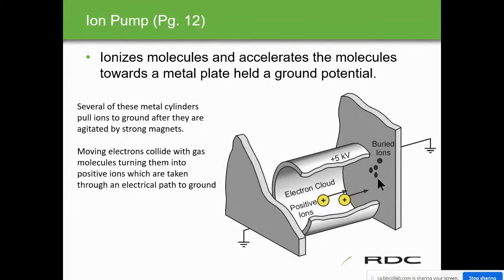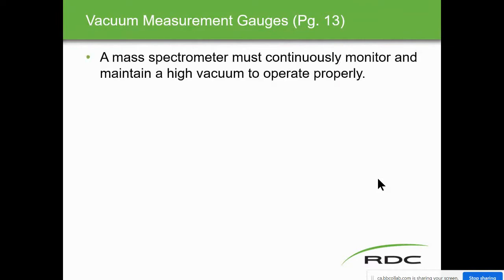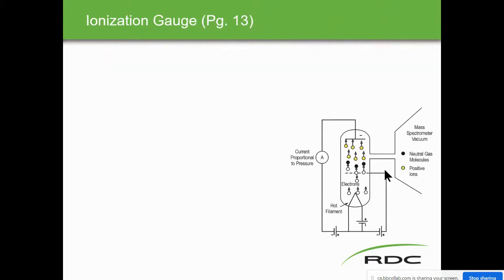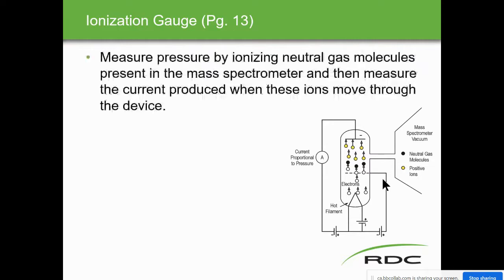The ion pump has no moving parts. It uses positively charged ions — ionized molecules accelerate toward a metal plate held at ground potential. With 5 kV applied, an electron cloud and positive ions all bleed to ground. Several metal cylinders pull ions to ground after they are agitated by strong magnets. Moving electrons collide with gas molecules, turning them into positive ions, which are taken through the electrical path to ground.